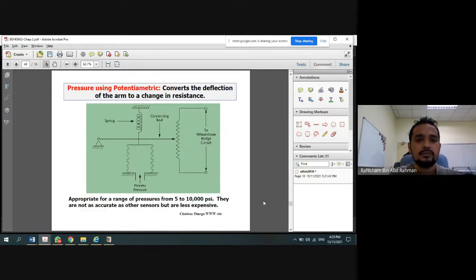Next, pressure using a potentiometric sensor. What we need to do is convert the deflection of the arm to a change in resistance. We have the pressure here, and we have the bellows. This will go up and down, which will change the spring. We have the connecting rod, and this connecting rod will move. This is the resistance.